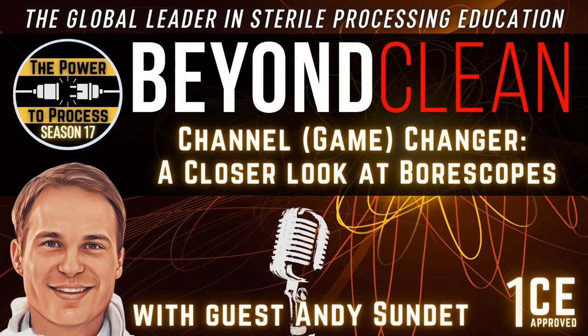I want to go back to that research piece. Those are striking results in how dirty these scopes are and the percentage of them. We're not talking about bad hospitals with bad names and bad ratings. We're talking about the entire industry across the board not being able to get these complex devices clean on a consistent basis. So I'm going to disagree with you a little, and in my personal opinion, if you can inspect, and it's a complex device that has historically had issues being cleaned, you should build that into your workflow and inspect that device every single time.